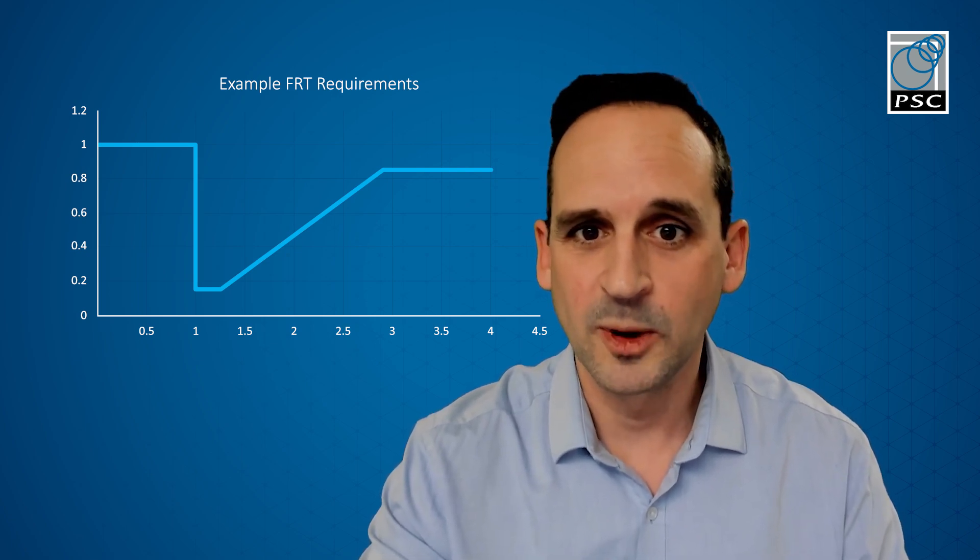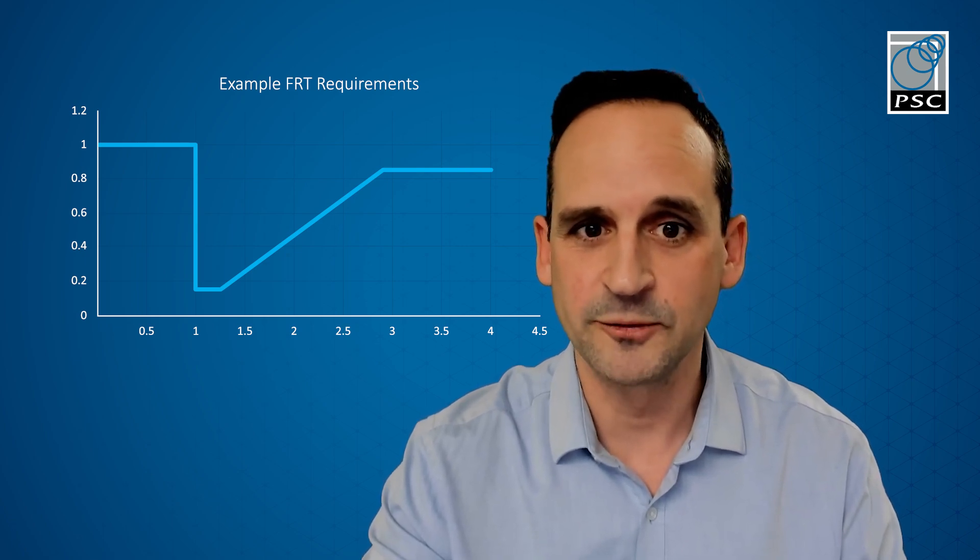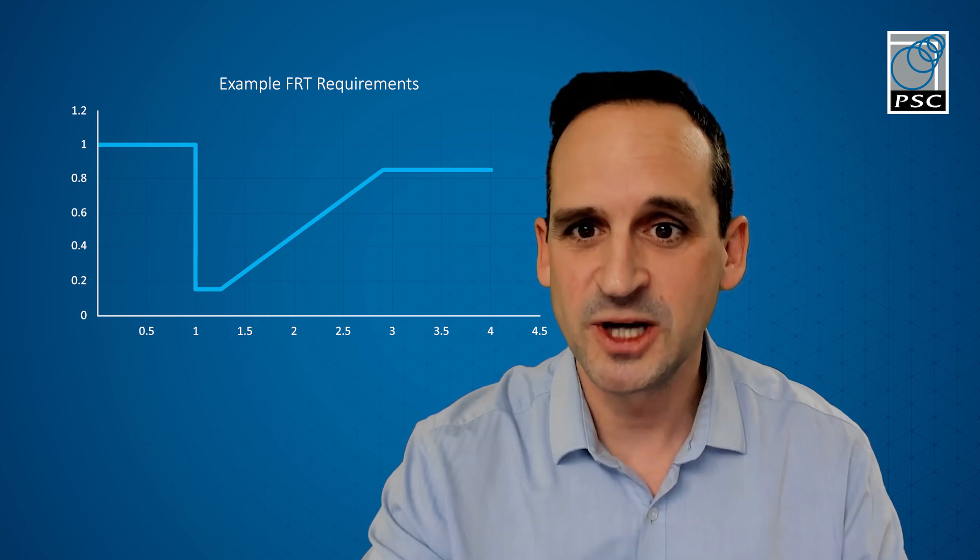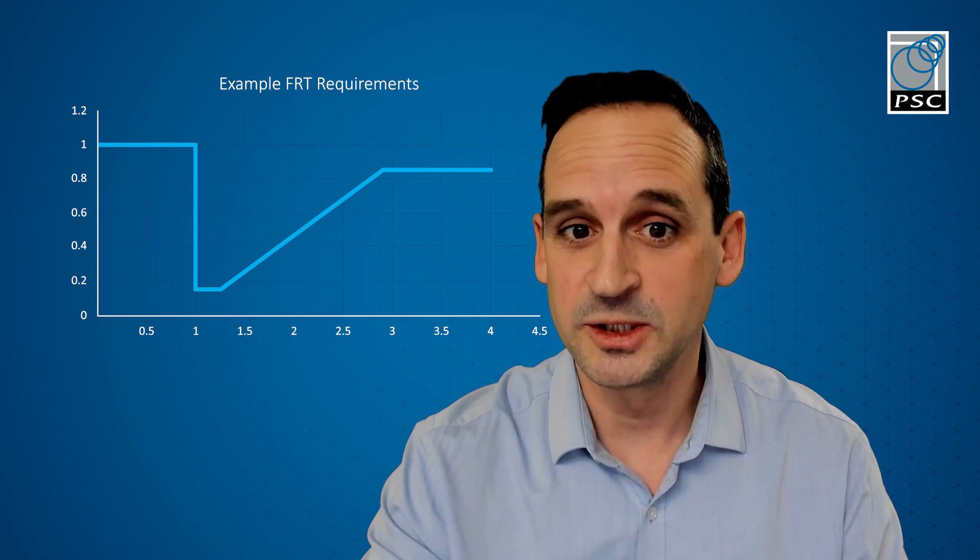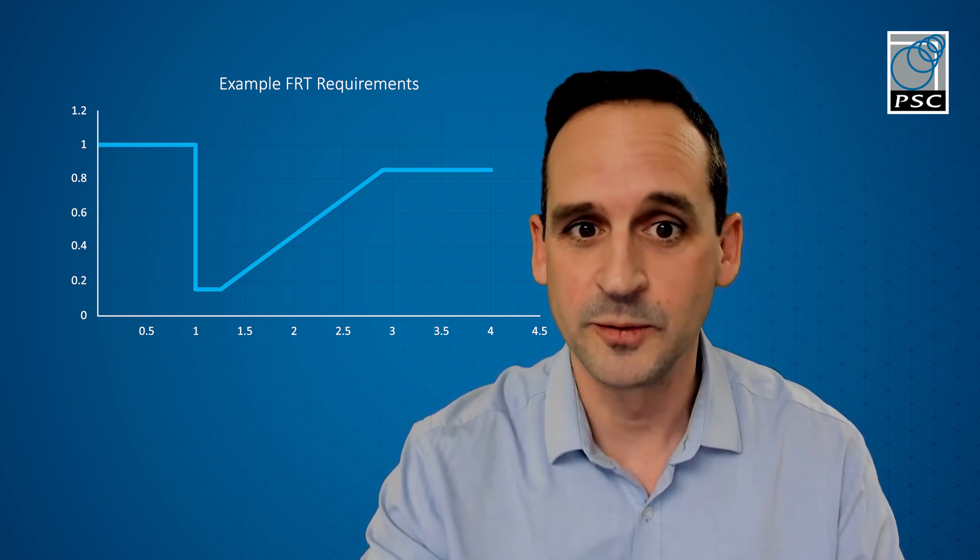The graph shows the lower limit of the voltage where the generator must remain connected during and after the fault. If the voltage at the connection point is above the line, then the generator must be able to ride through the fault and remain connected. It's worth mentioning that this type of study can be known as a low voltage ride-through as well as a fault ride-through study.